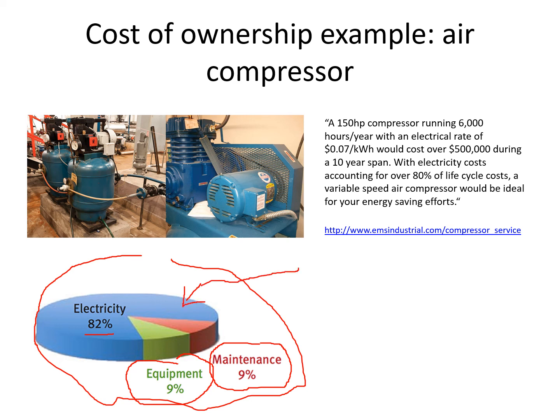The cost saving from having high efficiency will be much more than we will save by just buying a cheap motor in the beginning. Maybe if we buy a cheap motor, we pay not 9 points but something like 5 points, but then the electricity bill will be not 82 points but something like 95. So you see the point here.